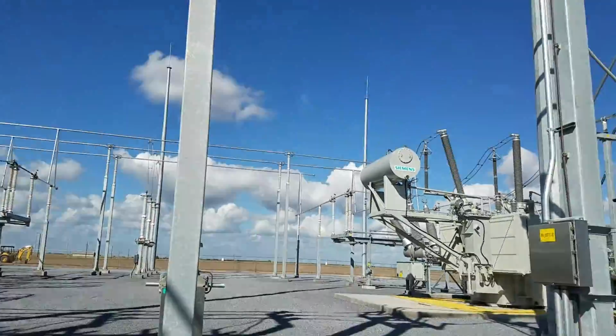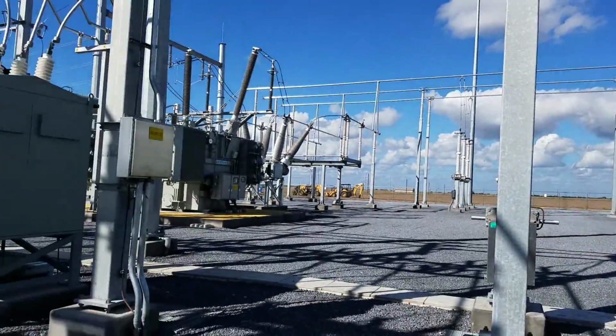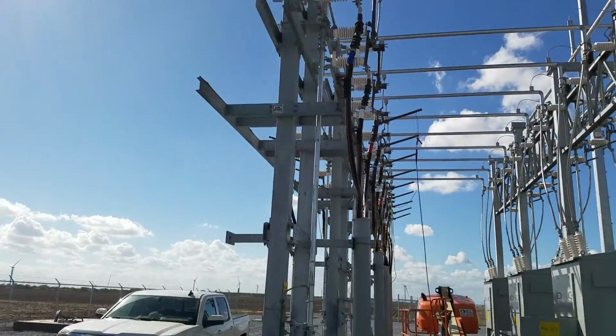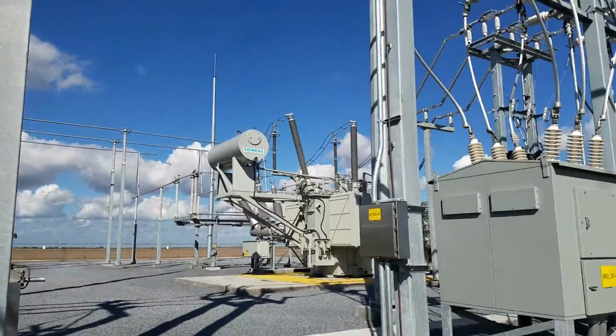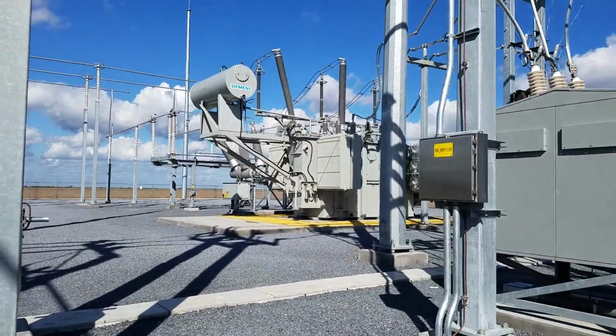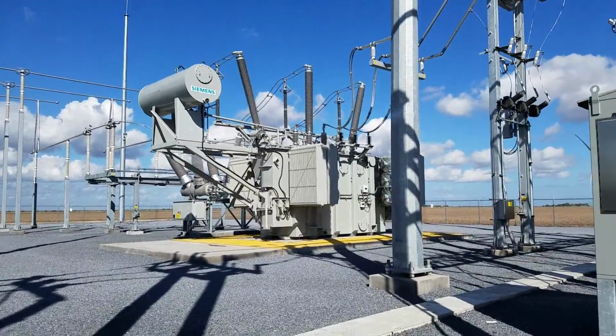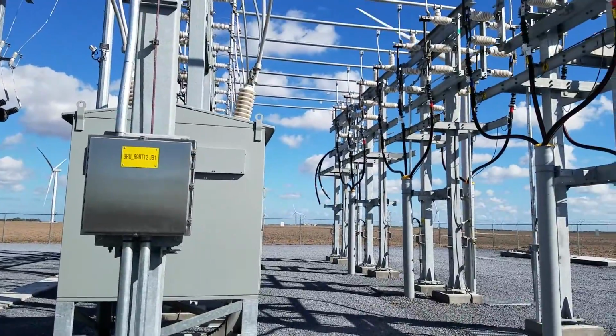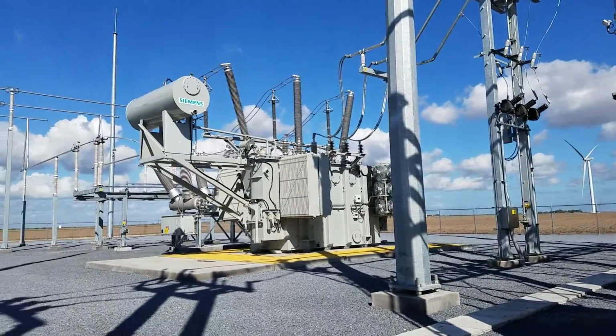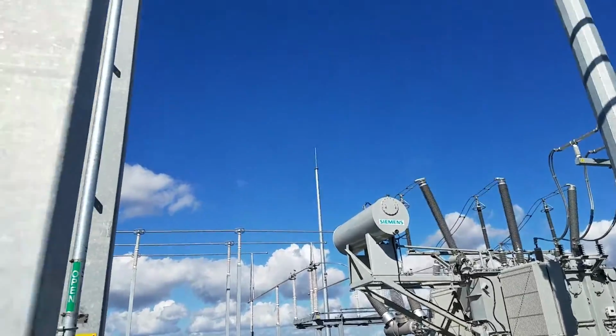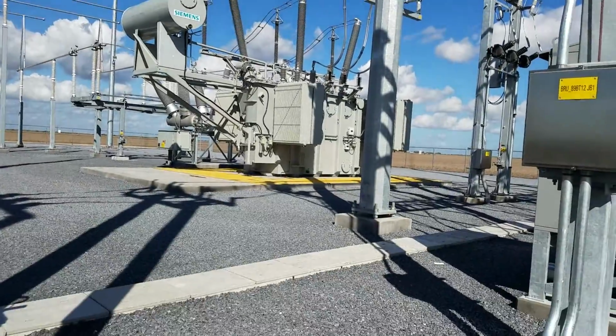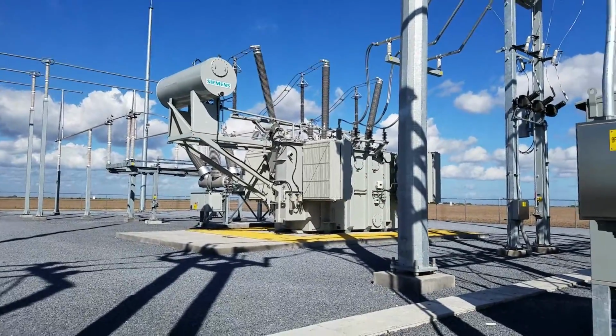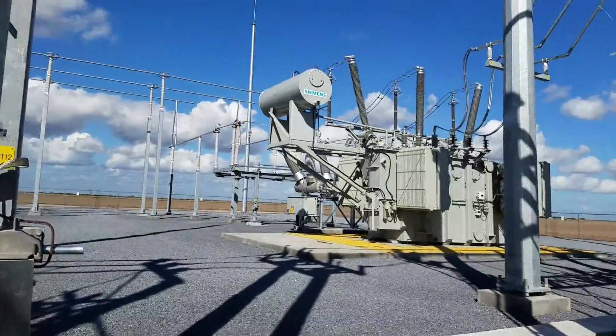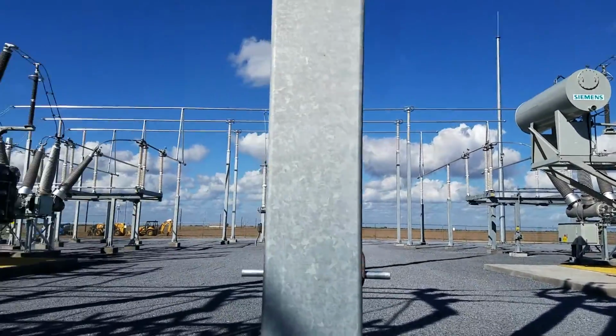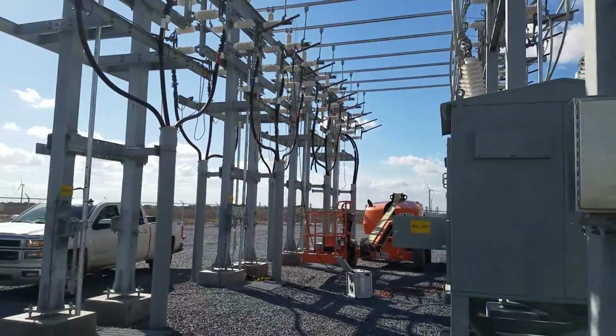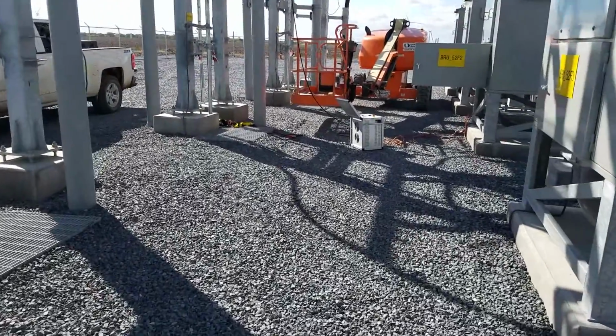But the one limitation to that is the MVA of the transformer. This doesn't mean that you can put all the power from this bay and add it to this transformer. You can't do that. That would overload and overheat the transformer. But say if you have a couple turbines down on this string and you have some room left in this transformer, then you could feed through this tie switch and basically get as much money as you can and keep as many turbines running as you can if you have any type of maintenance issue on one transformer or the other transformer or things like that. So that's really about it. We're just doing some VLF testing, which I'll talk about here in another video.